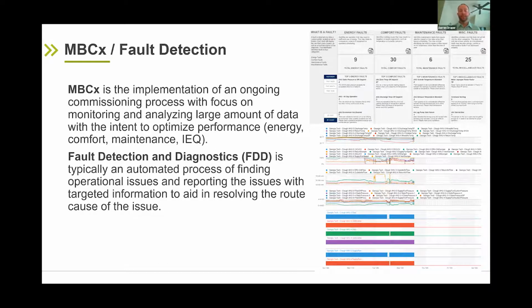Monitoring-based commissioning is really the implementation of an ongoing commissioning process, focused on monitoring and analyzing typically large amounts of data, and often condensing that down to information we can use to optimize performance of the building. That could be for energy purposes, comfort, maintenance, indoor air quality, indoor environmental quality, or a combination of those things.